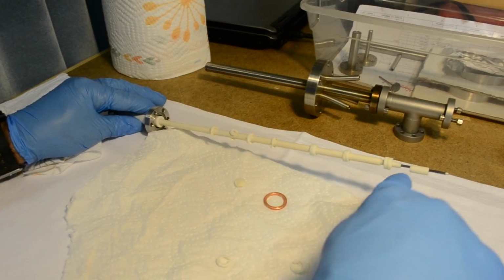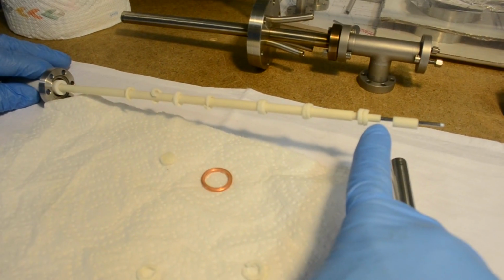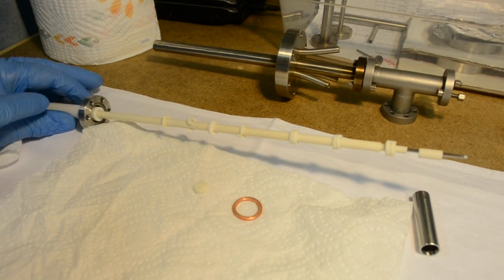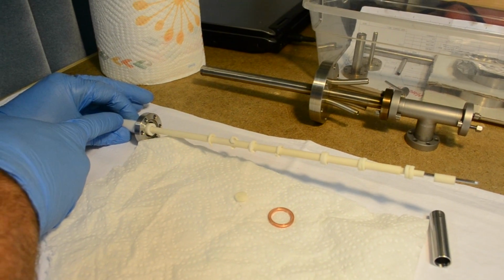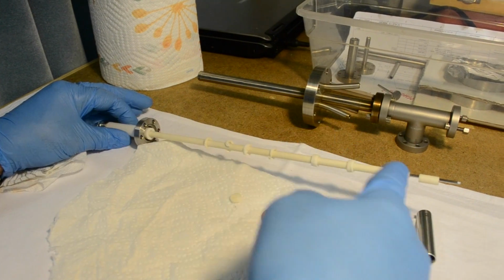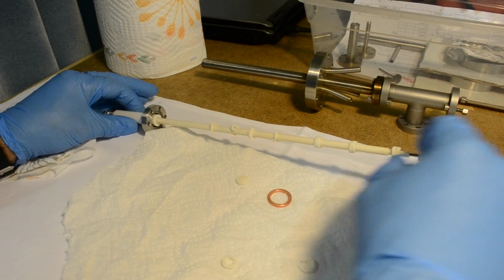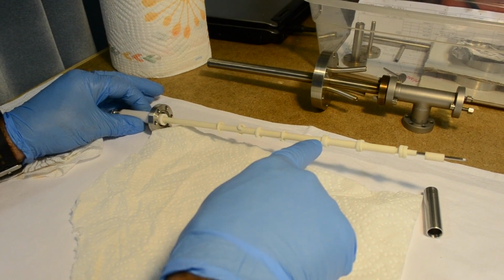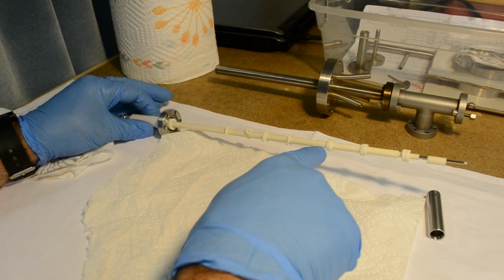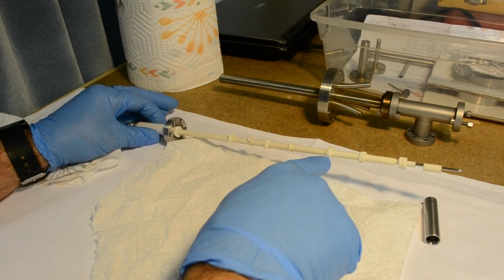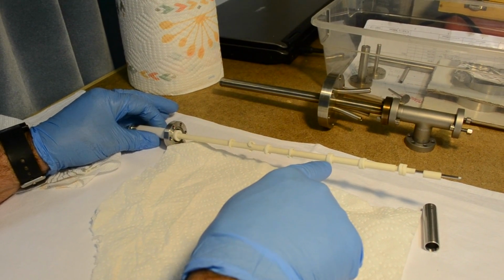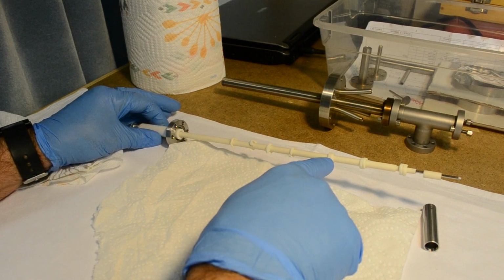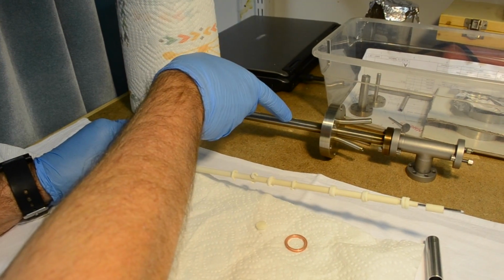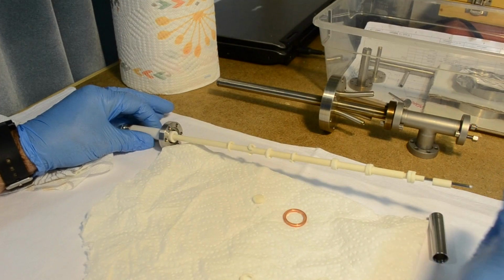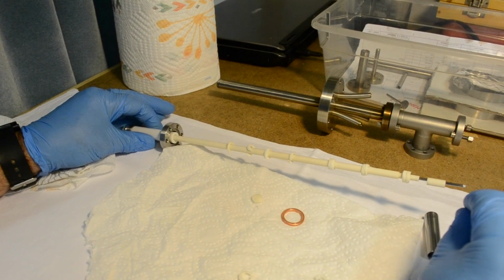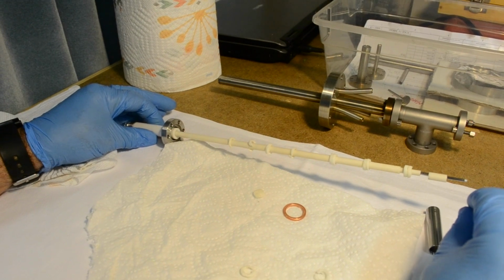So there's an inner ceramic tube that's this diameter, full length from a point approximately halfway inside the insulator of the electrode all the way down to here, and then there's the outer tube, which is continuous to this point, and then it has ceramic felt spacers, call them donuts or washers or whatever, that will contact the inside of the steel in order to keep the entire assembly as close to center line as possible down the tube.